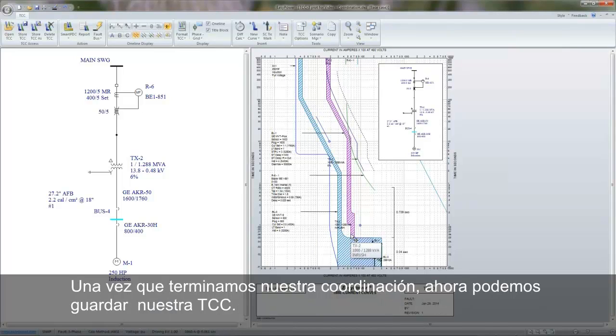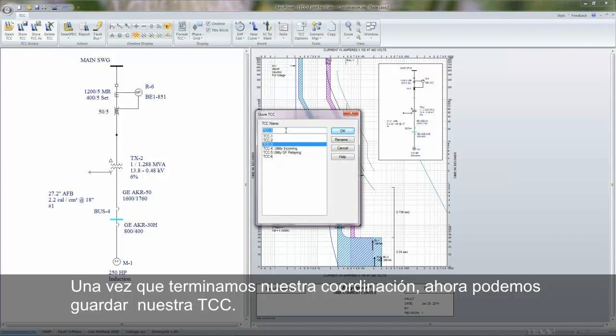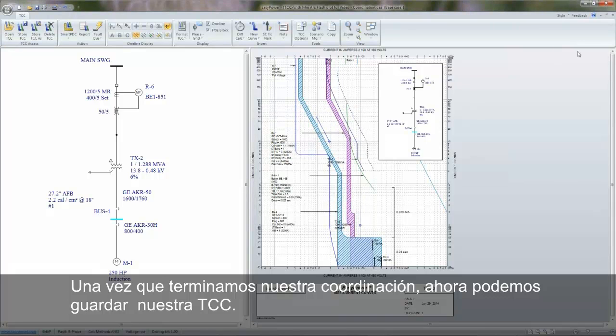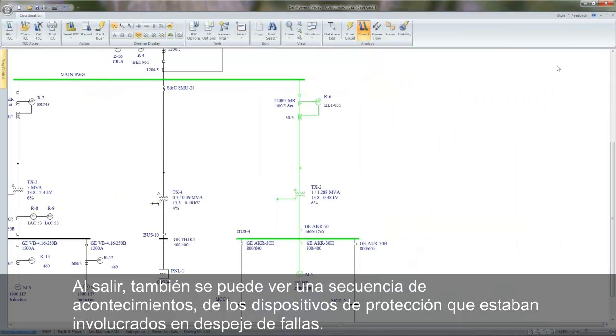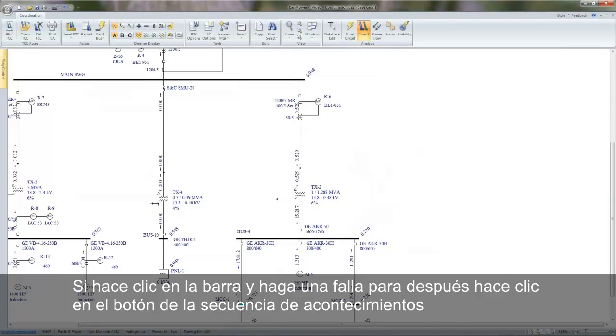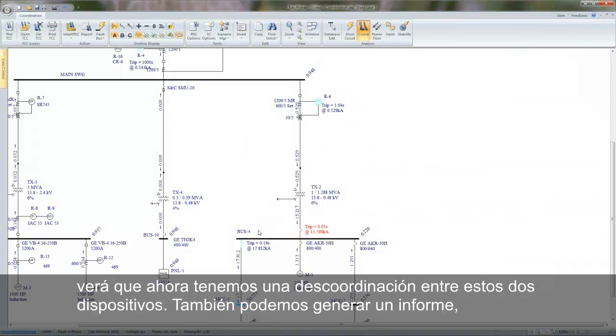Once we've completed our coordination, we can now save our TCC. Upon exiting, you can also see a sequence of events of your protective devices that were involved in fault clearing. If you simply click on a bus and fault and click on the sequence of events button, you'll see that here we have miscoordination between these two devices.